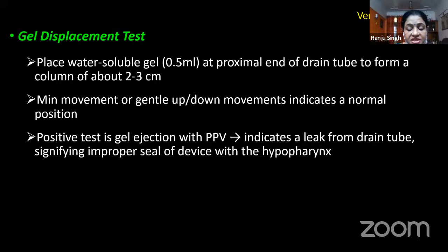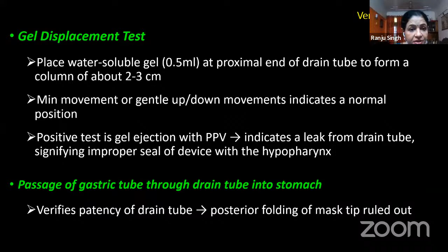indicating an improper seal of the device with the hypopharynx. The passage of the gastric tube through the drain tube is a very important indicator that the device has been correctly placed. It verifies the patency of the drain tube, and the posterior folding of the mask has been ruled out. Remember, I've seen many times that the device is put by the person who's managing the airway, and the insertion of the gastric tube is either left to the technician or somebody assisting that person. This is a very important step and gives you valuable information. So if the gastric tube cannot be passed down, it indicates trouble. It is a red flag which must be addressed. So it's an important step which should not be relegated to the background to somebody with little experience.